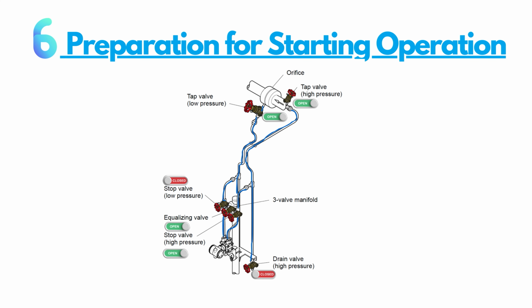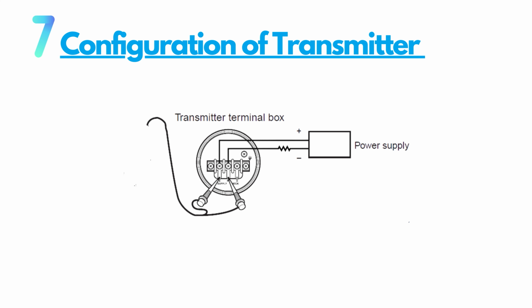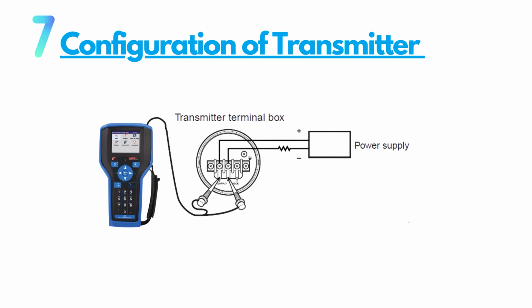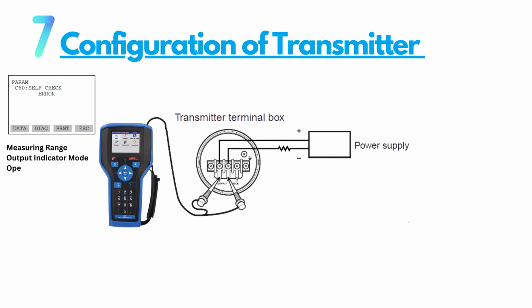Step 7. Configuration of transmitter. Turn on power and connect the HART communicator. Open the terminal box cover and connect the HART communicator to the supply plus and minus terminals. Confirm that the transmitter is operating properly. Check parameter values or change the set points as necessary. If the wiring system is faulty, communication error appears on the display. If the transmitter is faulty, self-check error appears on the display. The following parameters are the minimum settings required for operation: measuring range, output indicator mode, operation mode.